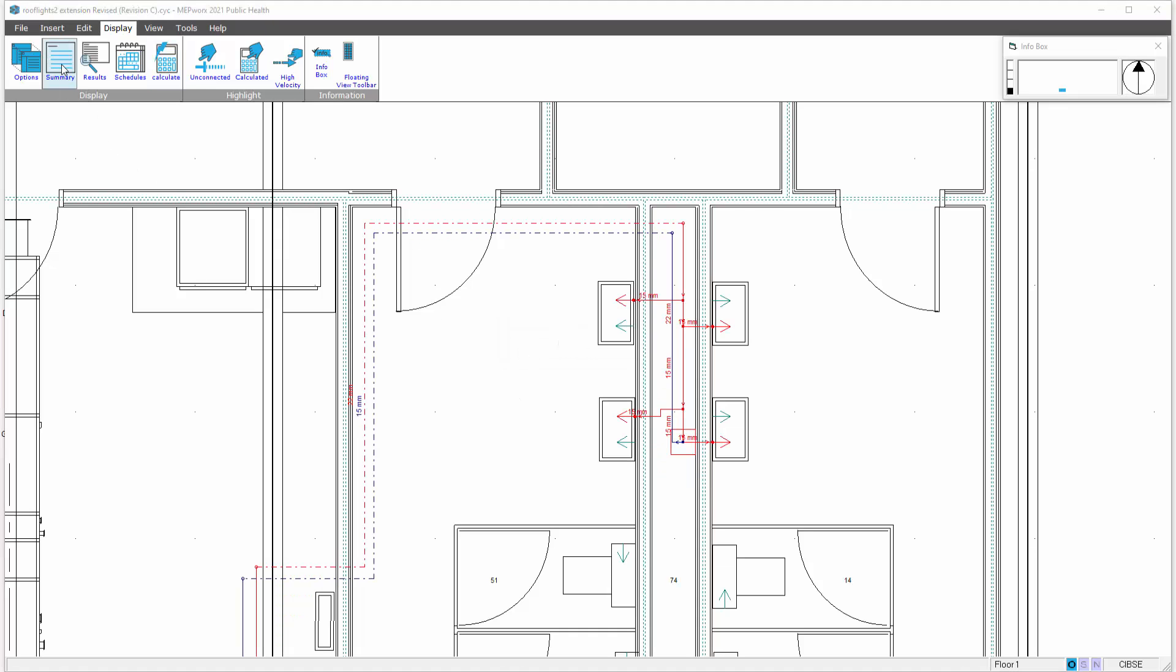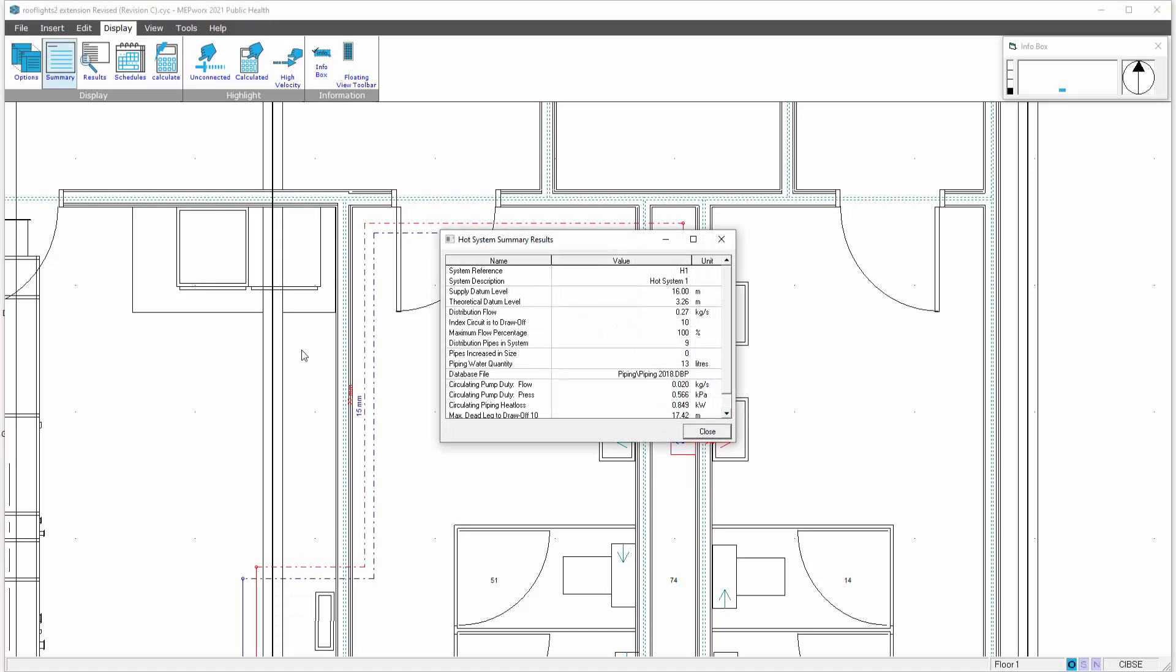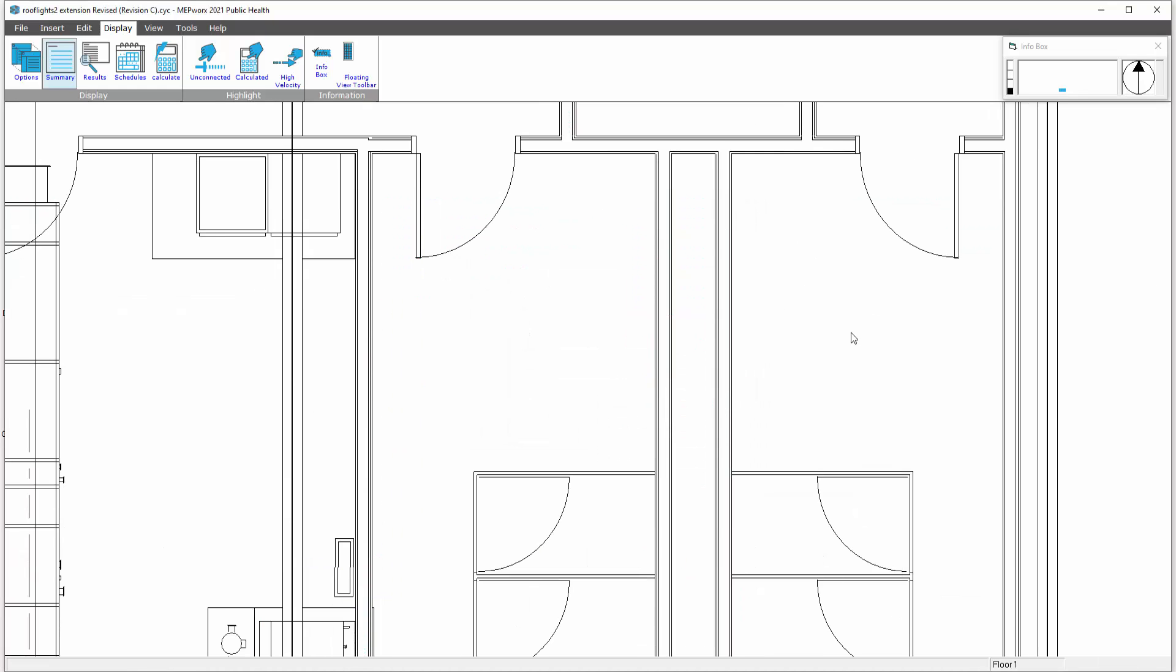And then summary, so you can see there's a vast difference. We've gone from 100 watts to 849 watts and we've got a pressure drop now of 0.566 kPa as opposed to two and a half. You can see the effect of trying to maintain that delta T of 10 degrees, it's increasing the flow rate. That is how you basically put together a circulating return system.